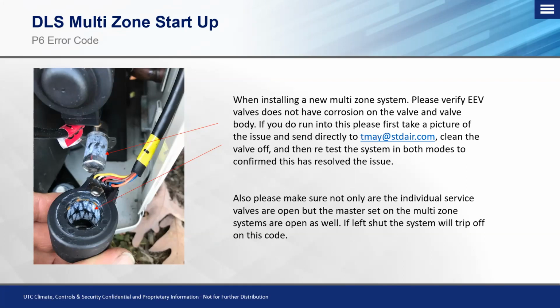This is a documented issue that we're documenting with Carrier and obviously working to resolve. But it is something that we found in a few circumstances. So again, if you have a situation like this, please take a picture of it. And then in order to resolve it for the time being, just take a wet rag with some soapy water, clean off the inside of the indoor or the EXV coil, and also clean off the post.